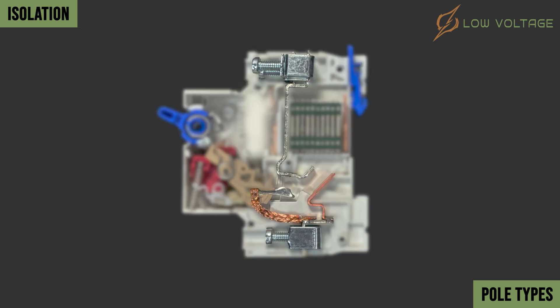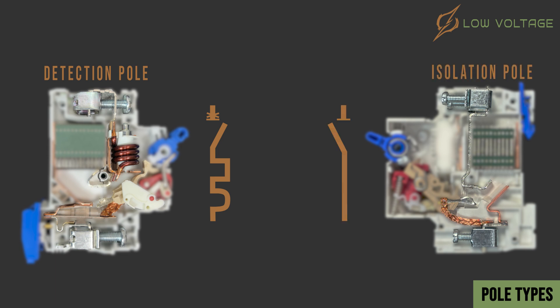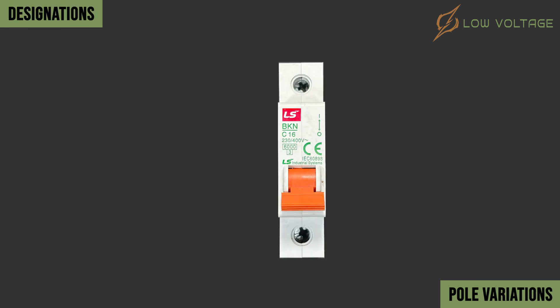When the thermal and magnetic units are not installed, then the pole will not detect faults, and will not offer protection — it will be only for isolation. Now we can say, when the protection units are installed, then we have a detection pole having this symbol. Now we know the difference between a detection pole and an isolation pole. Let's discover the pole variations in the real world.